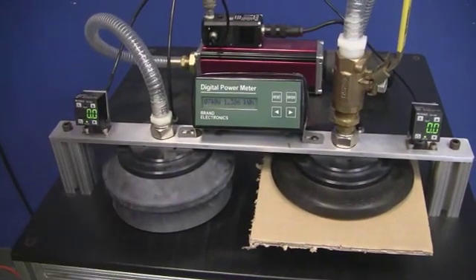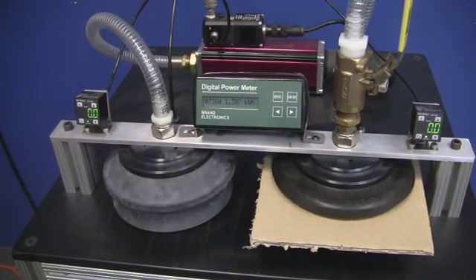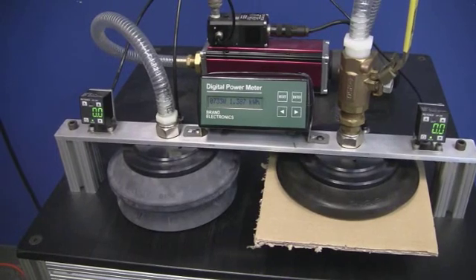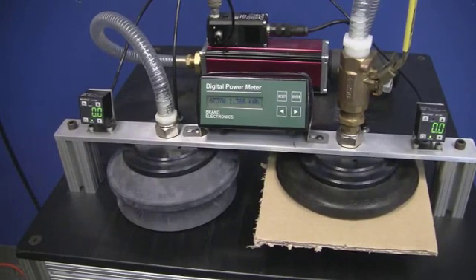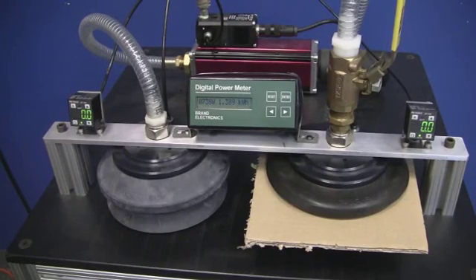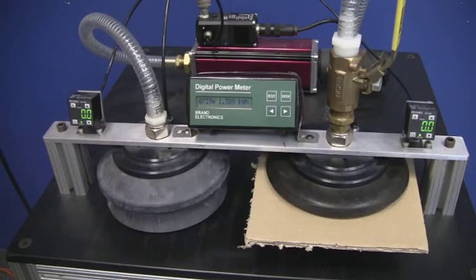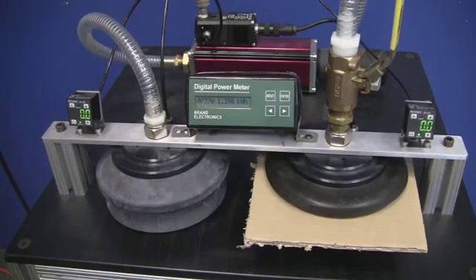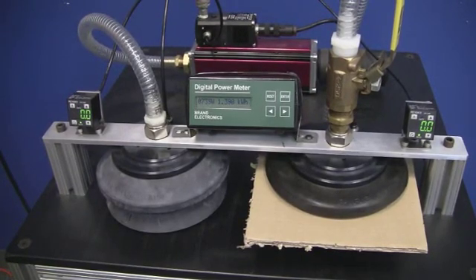Now when we put something on the cup, it's when the vacuum system's in demand and doing work. The energy input rises. In this case, we're handling a corrugated material, which is porous. So the vacuum level isn't really as deep as a sealed system, but the pump is now using about 740 watts, which is much higher than the rated three-quarter horsepower.